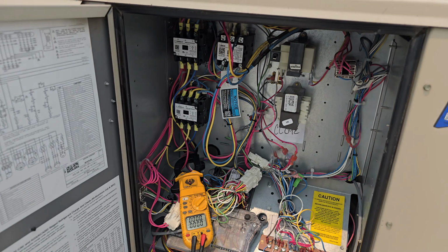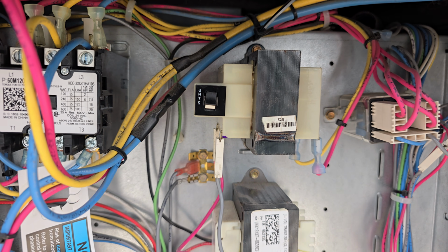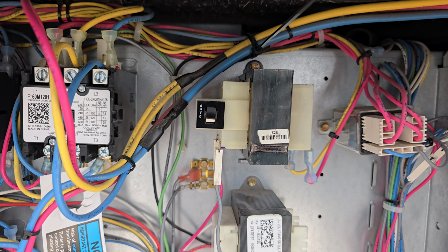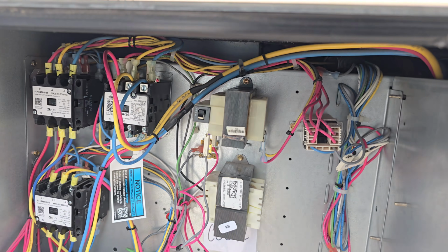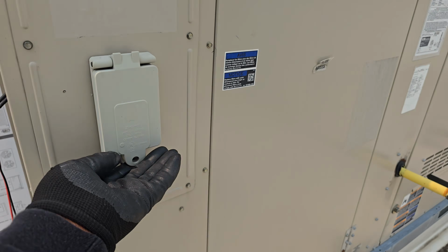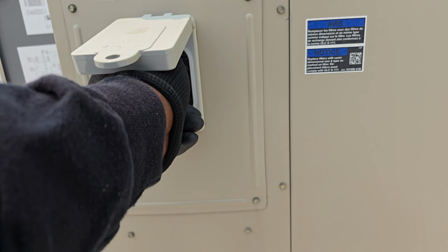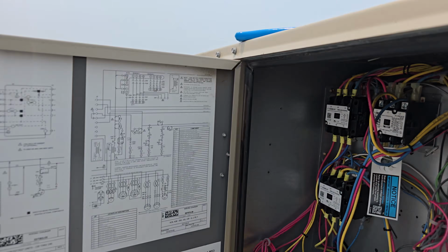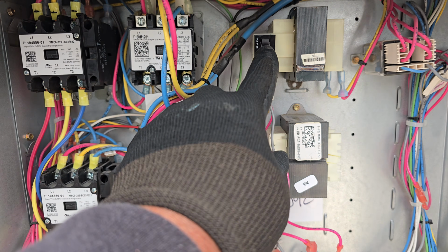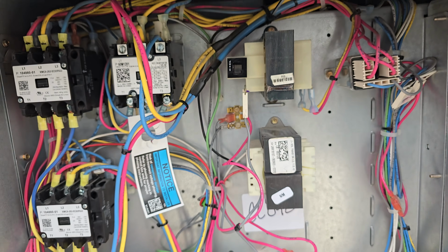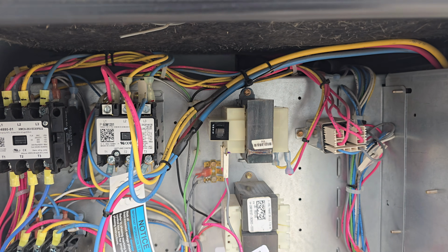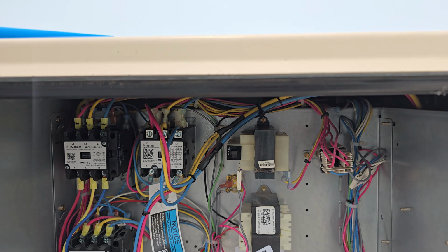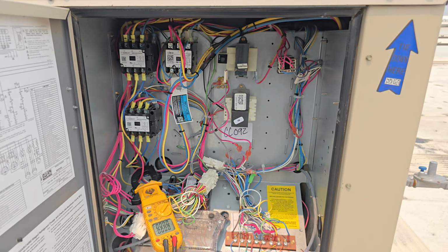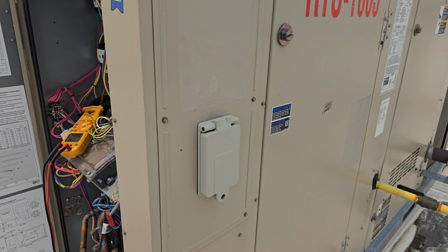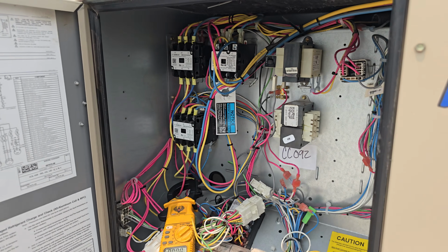So I'm going to have to reset this transformer. To reset this transformer, first I have to turn it off from the main here. So I'm going to turn it off here. Okay, now I'm going to push it to reset. I'm going to wait a few minutes to see if the coil is hot, so it can cool down. So wait a couple of minutes. Now I'm going to turn it on. Now that I reset it and turned it on, my unit comes on.